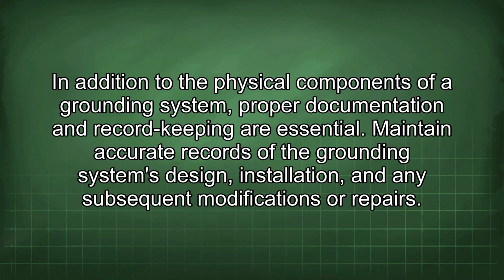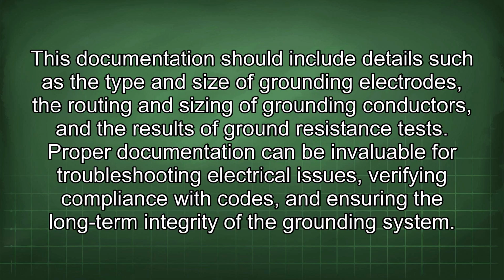In addition to the physical components of a grounding system, proper documentation and record keeping are essential. Maintain accurate records of the grounding system's design, installation, and any subsequent modifications or repairs. This documentation should include details such as the type and size of grounding electrodes, the routing and sizing of grounding conductors, and the results of ground resistance tests. Proper documentation can be invaluable for troubleshooting electrical issues, verifying compliance with codes, and ensuring the long-term integrity of the grounding system.